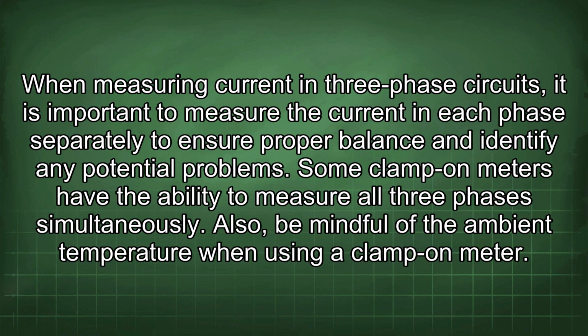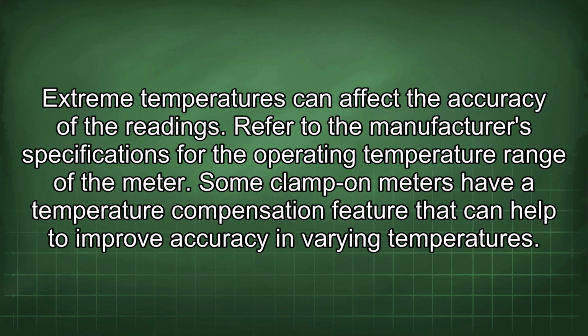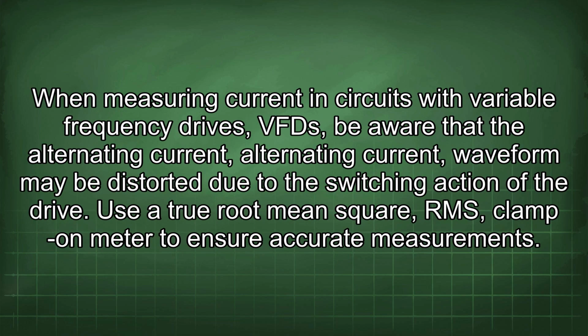When measuring current in three-phase circuits, it is important to measure the current in each phase separately to ensure proper balance and identify any potential problems. Some clamp-on meters have the ability to measure all three phases simultaneously. Also, be mindful of the ambient temperature when using a clamp-on meter. Extreme temperatures can affect the accuracy of the readings. Refer to the manufacturer's specifications for the operating temperature range of the meter. Some clamp-on meters have a temperature compensation feature that can help to improve accuracy in varying temperatures. When measuring current in circuits with variable frequency drives (VFDs), be aware that the alternating current waveform may be distorted due to the switching action of the drive.